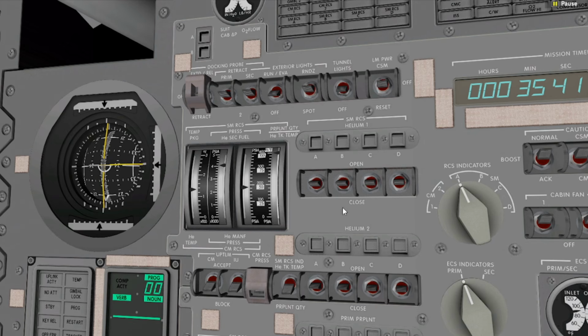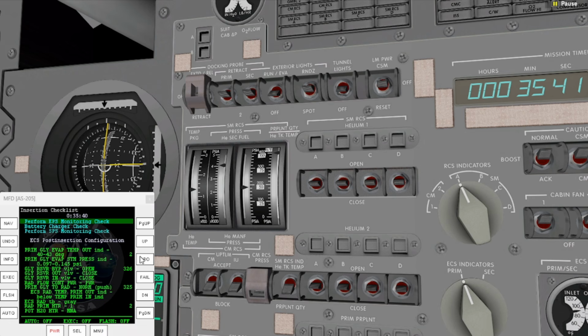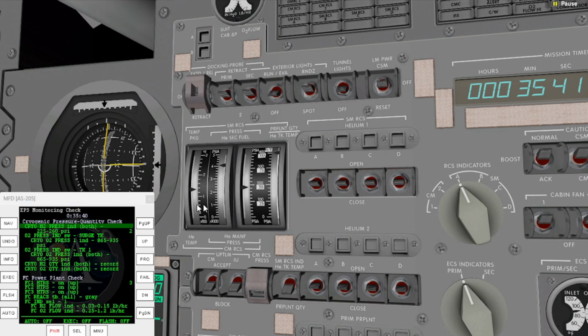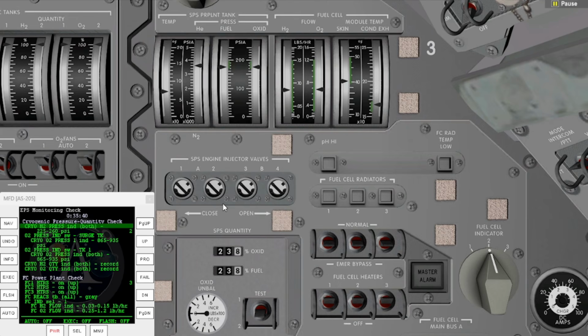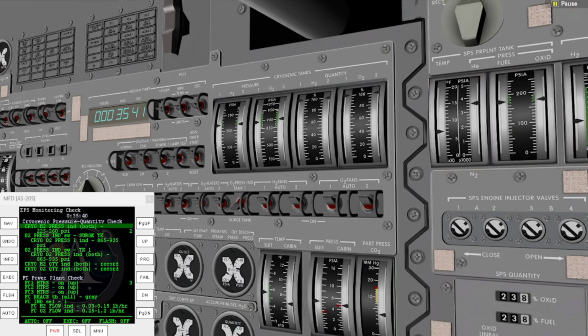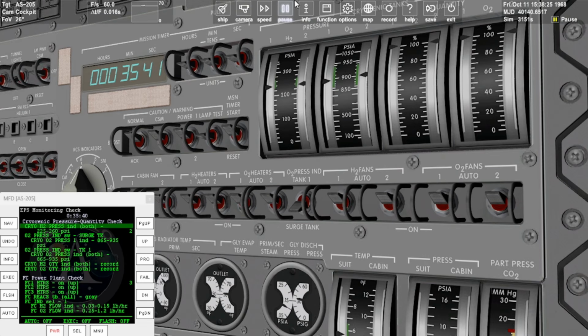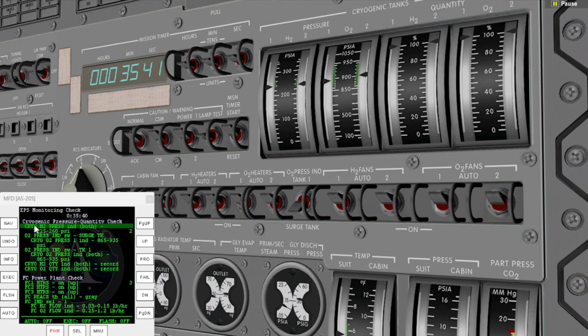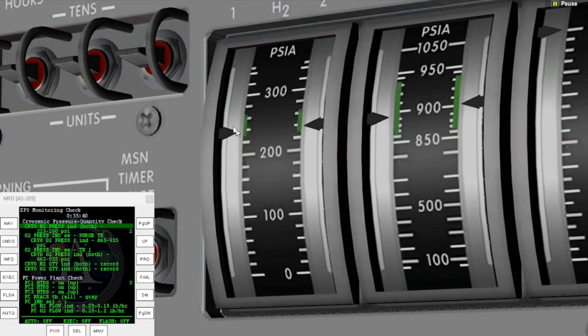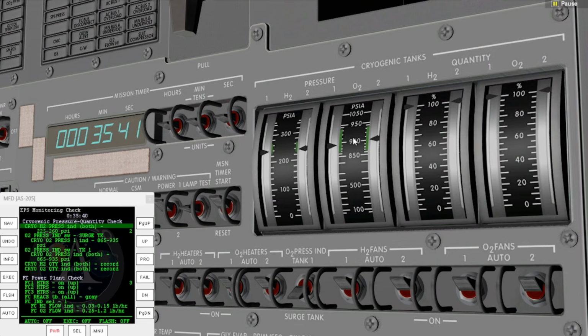All right. The next one will be the electrical power system monitoring check. This will go through all of our power generation systems and run a checkout on them. So the first thing we're gonna do is check our cryogenic H2 pressure indication. Both should be 225 to 260. We've got a nice green band, so we already know that that's good.